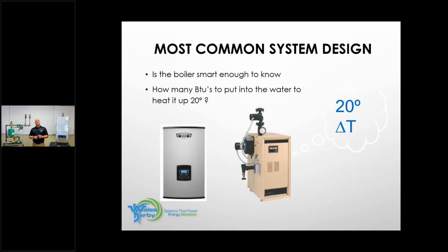So most common delta T's, here we are. Again, there's a cast iron boiler. I don't care what color that jacket is, guys. That's cast iron. It's designed around a 20-degree delta T. I want to see if my laser will work. Okay, so here's the supply header. We're going to be coming out of here. We're going to go out, go through our heat emitters, up through our heat emitters. We're going to come back down, and we're going to tuck into this return pipe right here.